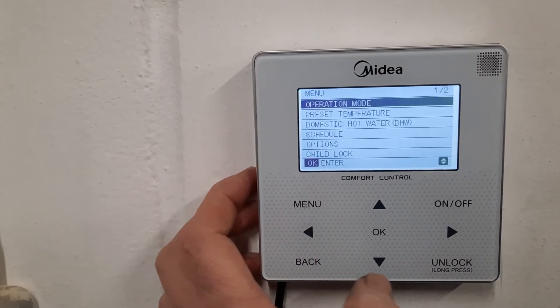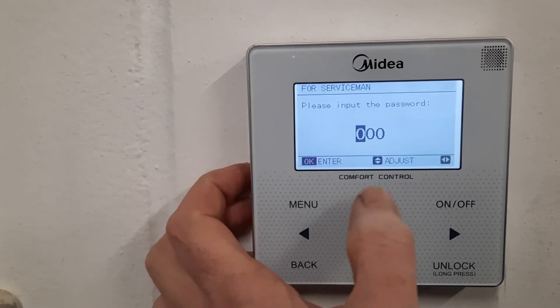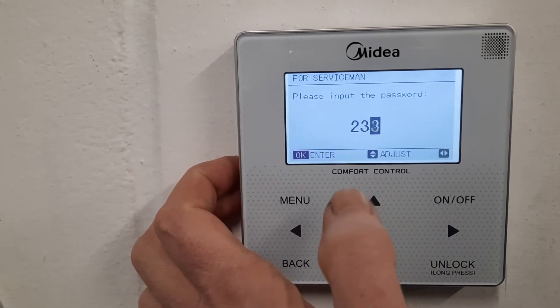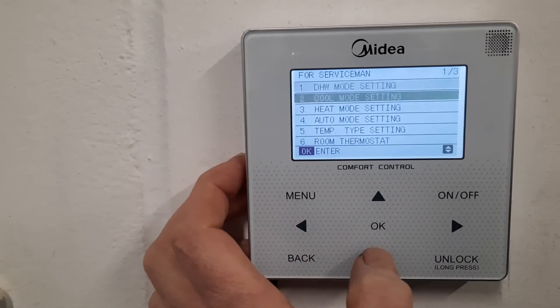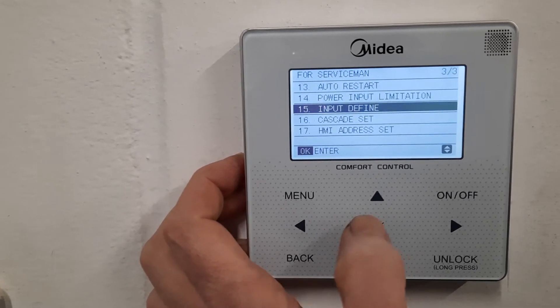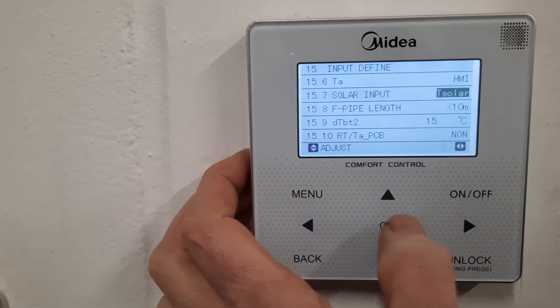What you need to do is go to Menu, down to For Serviceman, press OK, password 2-3-4, press OK. Now go down to 15, which is Input Define, then go down to 15.7 Solar Input.